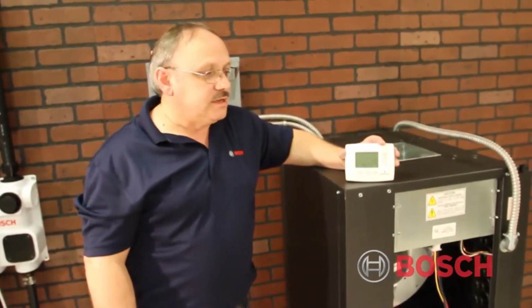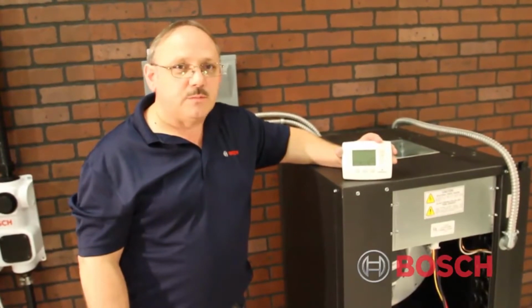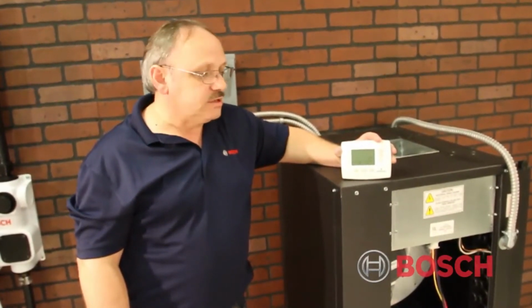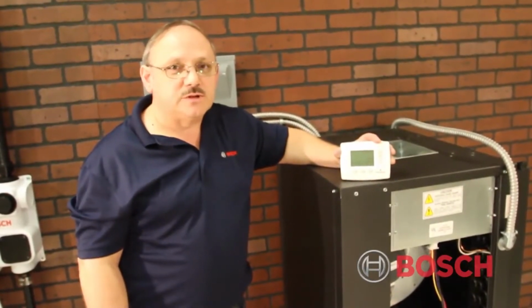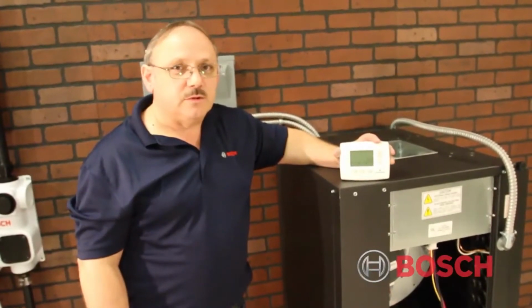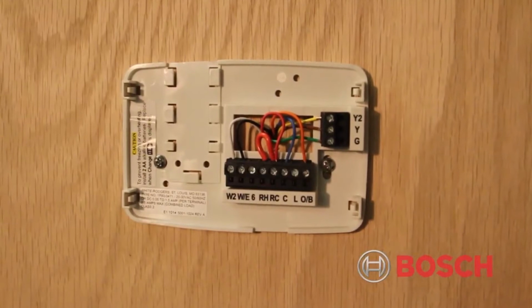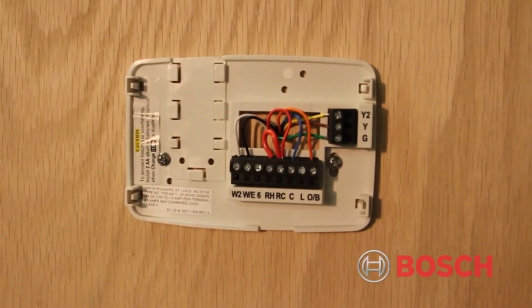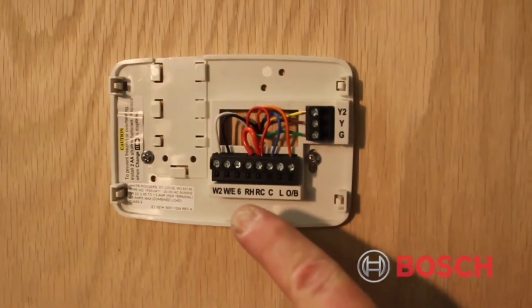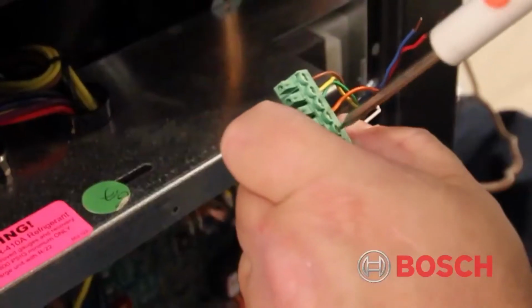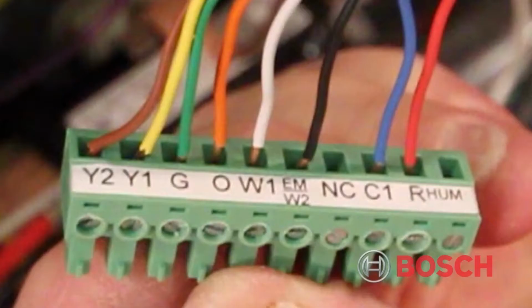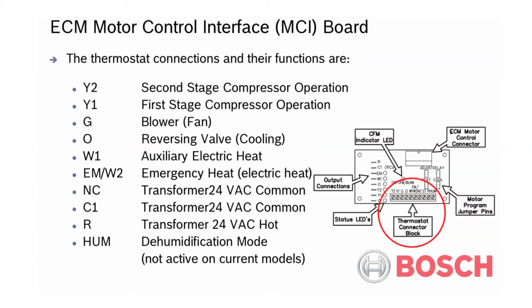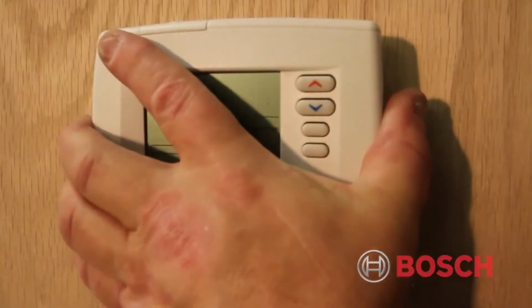Now, if you're in an existing home and just replacing a system, the thermostat will already be located in the home somewhere near the return air, and you'll just simply have to replace that control. If you're installing a system in a house that does not have an existing system, then you'll have to route your thermostat control wire to the location where you want to mount that thermostat. We have already routed our thermostat wires to where we want to mount our thermostat near our return air location. And we've routed our thermostat wires through the hole in the back of our thermostat subbase. And we've made our connections to the thermostat subbase electrical connections. You want to make sure that the wires that are connected here match up with the same terminals on the TA025 unit so that we get proper operation from the thermostat. And once you've made your electrical connections, you can simply attach the thermostat to the subbase.